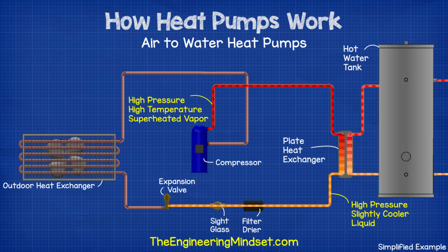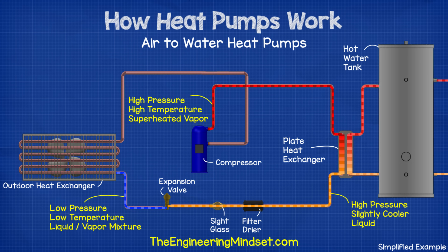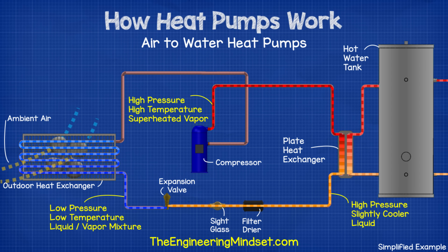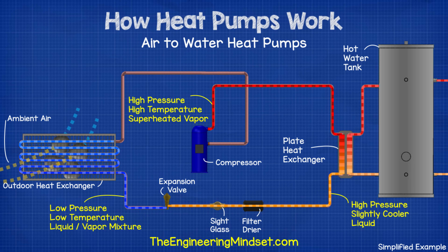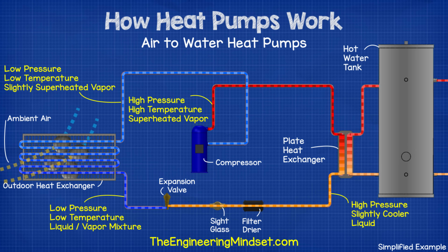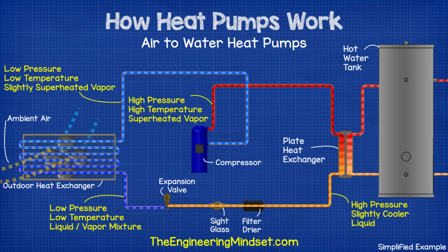The refrigerant then passes through the filter dryer and the sight glass, and then into the expansion valve. The expansion valve causes the refrigerant to become a part liquid, part vapor state at a low temperature and pressure. It then passes through the outdoor heat exchanger, where the outdoor ambient air causes the refrigerant to boil. The refrigerant then leaves at a low pressure, low temperature, slightly superheated vapor, and is then sucked back into the compressor to repeat the entire cycle. The hot water tank then provides hot water to the radiators, sinks, and showers within the building.